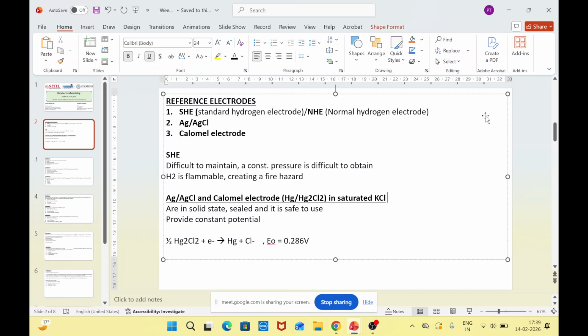The answer is, what usually happens is, the Cl minus ions that are there within these liquids in both these calomel electrodes, there are chances that over a long period of time, along with the continuous operation of these reference electrodes, these liquids may evaporate. So due to that, the concentration of the Cl minus ion, or to put it specifically in electrochemistry terms, the activity of the Cl minus ion usually gets altered.